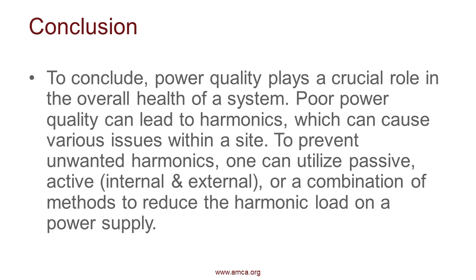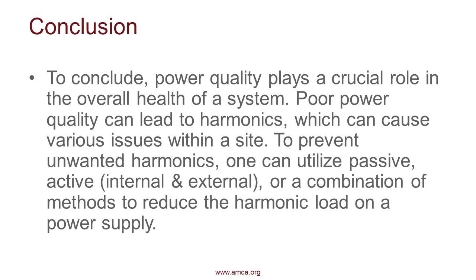our system. We know that harmonics can lead to issues and problems within our site, and to prevent these unwanted harmonics, we can utilize different passive, active, or combination of the two filters to reduce that harmonic load on our power system, our power supply.